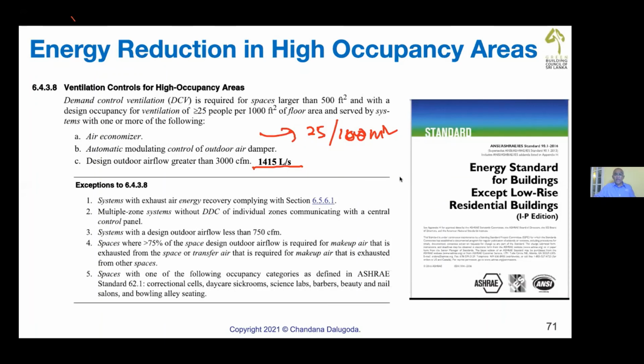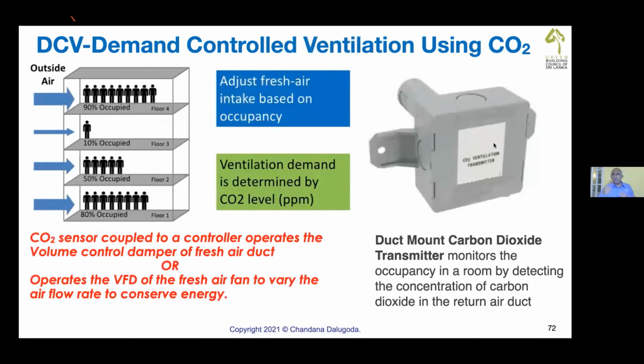How do we do that? We use a CO2 sensor. By detecting CO2, we change the fan speed. That will have an enormous power saving. For fresh air, for car parks, we use CO sensors. Nowadays, in car parks, fans are on 8 hours. When you put these CO sensors, total running hours may be 2 hours, 3 hours. Enormous power saving means your energy consumption is lower, your carbon footprint is lower.